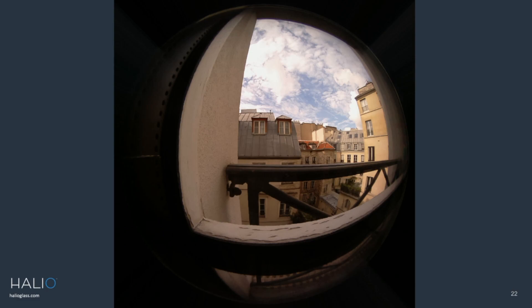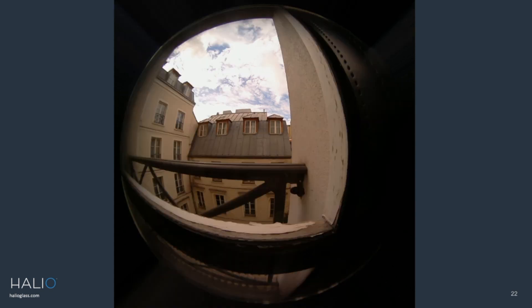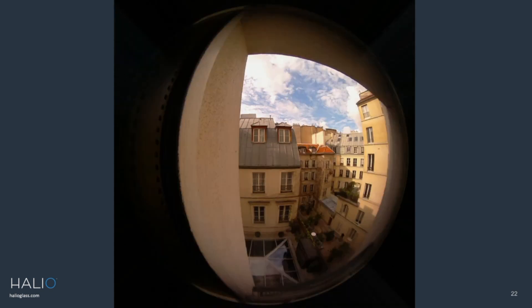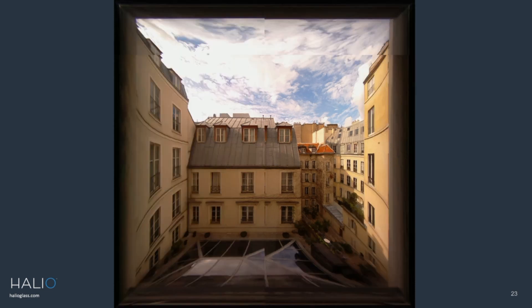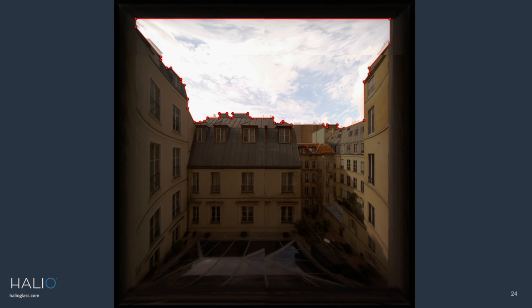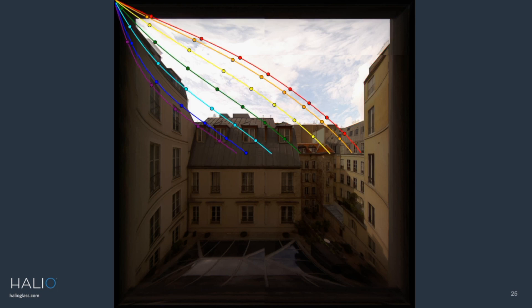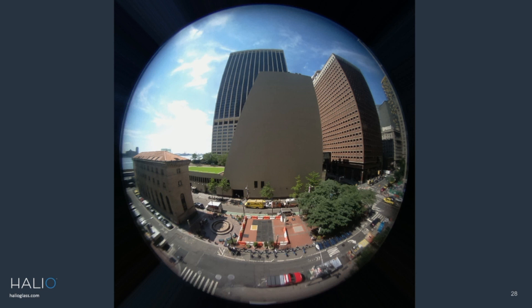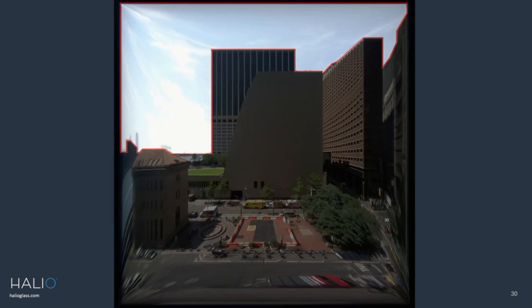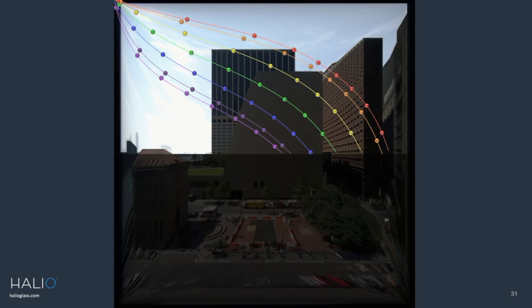I also have some examples. This one is from the hotel I'm staying in this week — a room that looks out into a courtyard. I take four photos at different corners of the window to get good coverage, then remap and merge them into the orthonormal format, trace around them, and overlay the sun path to see when and what time of year shadow will be cast onto the window. That map is then uploaded into a control system to control a shade, blind, or electrochromic window. Another example is a New York City office building — reprojected, traced, with the sun path, and then the final map.